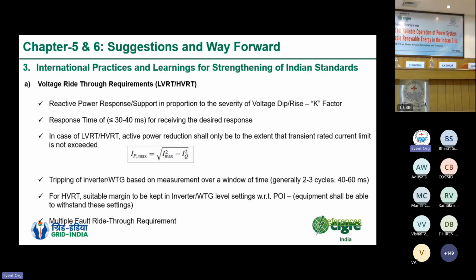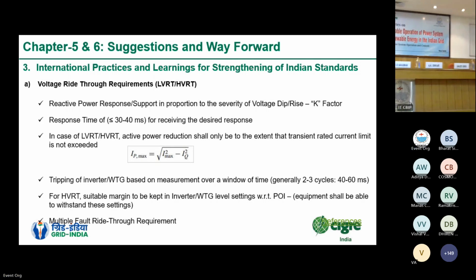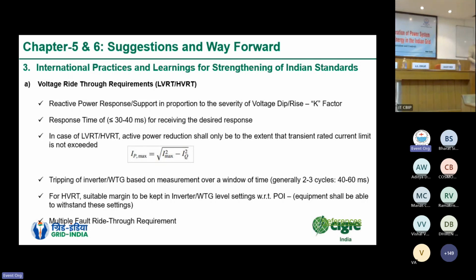Again, for the HVRT, a suitable margin shall be kept so that there is always a gap between the voltage at the point of interconnection and the voltage at the inverter terminal. This gap should be taken care of and appropriately specified to provide more clarity. As of now, these things are available in our standards, but further clarity can be added based on what is available in other power systems.